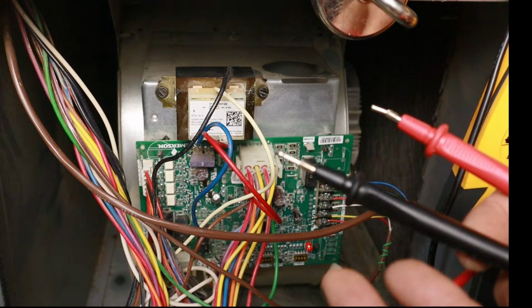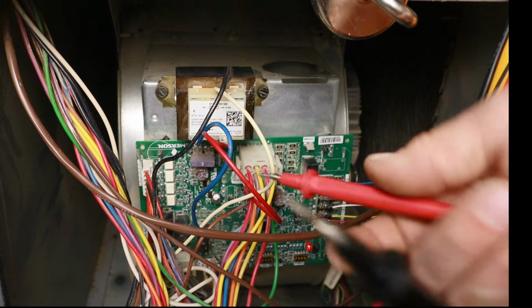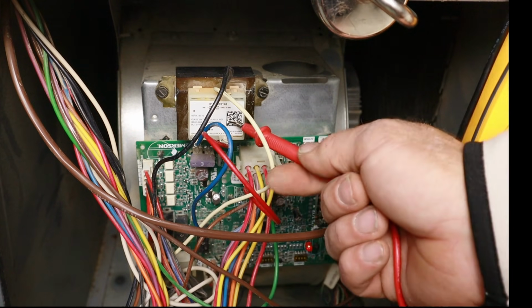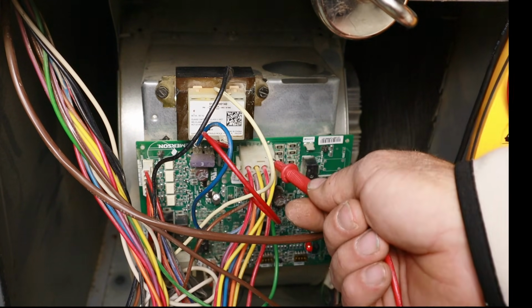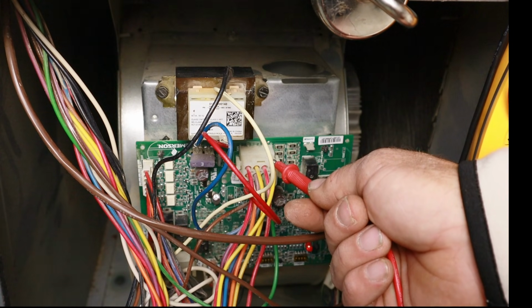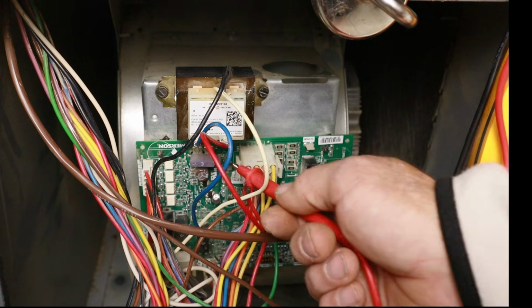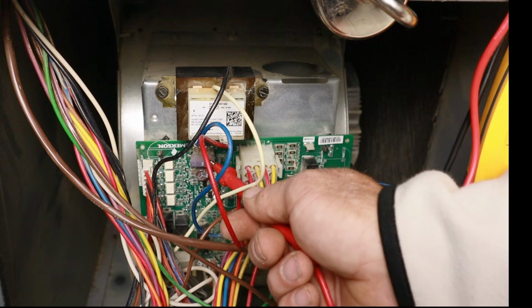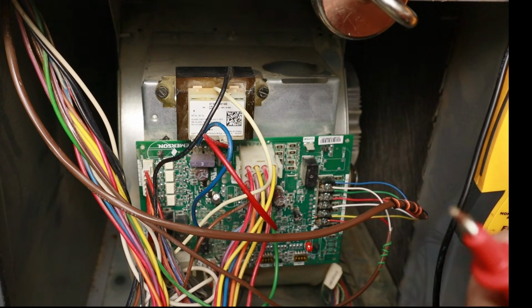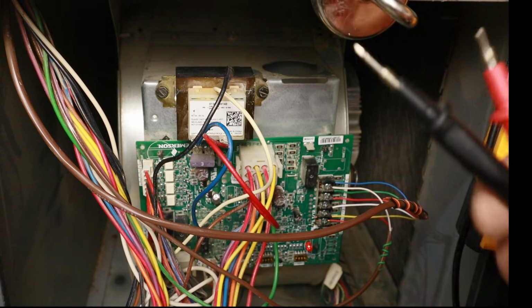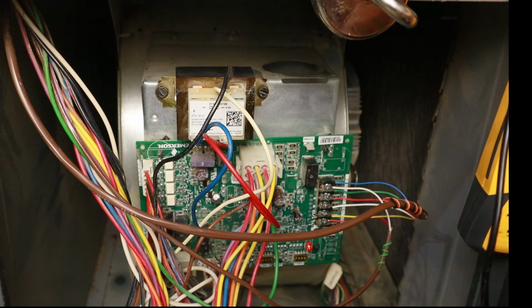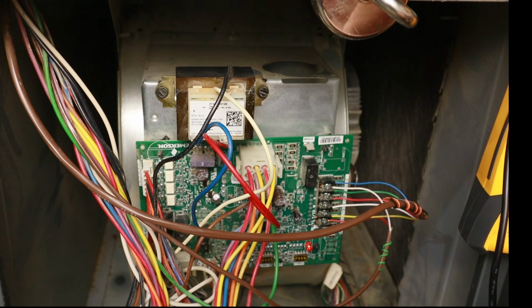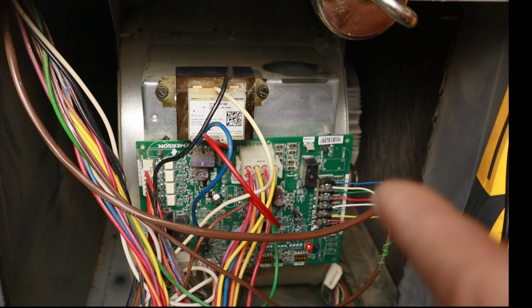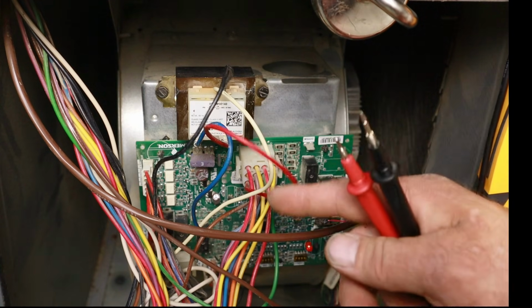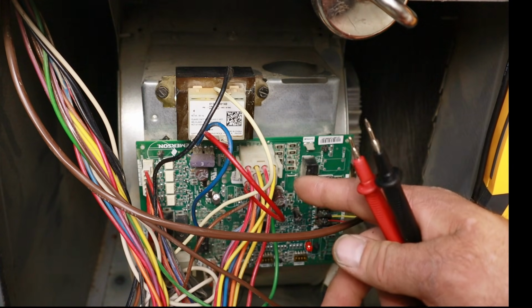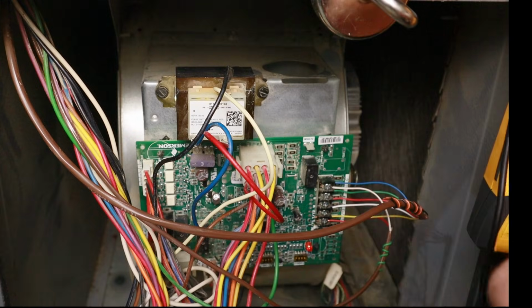But there's another way to do this, just from experience I'll show you guys. Whenever you have 24 volts coming off a transformer and going back to your control board, the first place it will always go is to the fuse. So we could see our little 3 amp fuse right down in here. Now some schematics might show this, some will not. The schematic we're working with today doesn't actually show that, but with all furnaces, that 24 volts coming off the transformer back into your control module, the first place it's going to go is to that fuse.